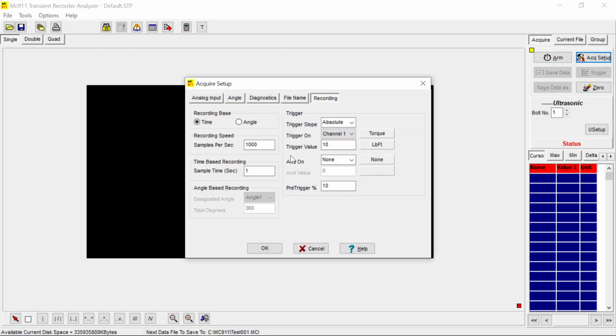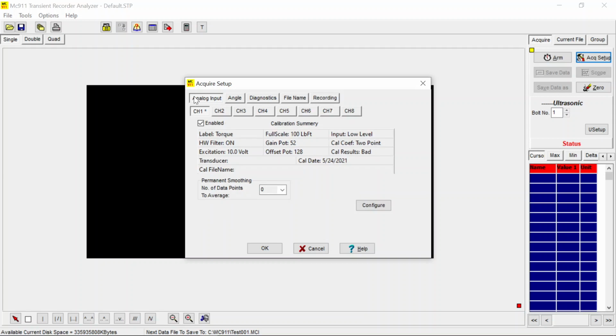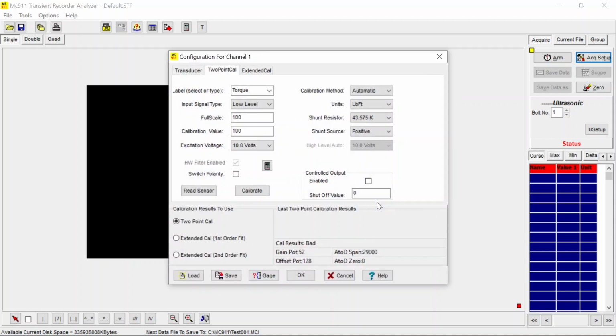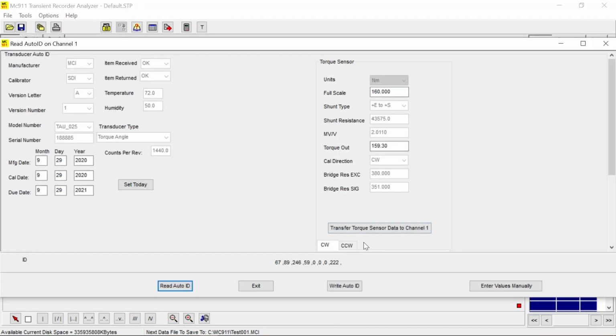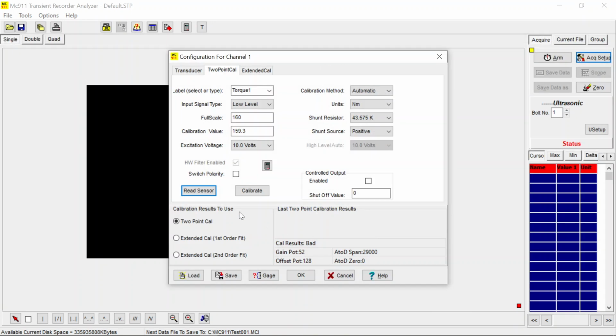First of all, we have to calibrate the torque angle transducer and set other parameters for data collection. Let's start with that. Acquire setup. We start from the analog input. We have channel 1 enabled, which is torque. Click on configure, and let's read the sensor. Read the sensor, transfer the information. So we have 160 Newton meter, that's the units.